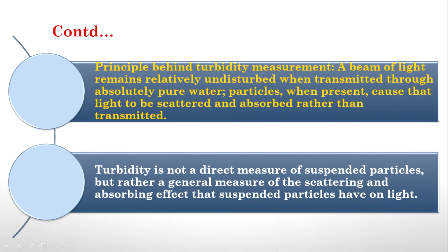The main principle behind this turbidity measurement is that a beam of light remains relatively undisturbed when transmitted through absolutely pure water. Particles, when present, cause that light to be scattered and absorbed rather than transmitted. So this is the main principle. We will compare the absorption or transmission or reflection of light from a pure water and from a turbid water. The comparison will give the relative turbidity. So water, if it is not turbid, will transmit all the light. And it is not a direct measurement of suspended particles, but rather a general measurement of the scattering and absorbing effect that suspended particles have on light.